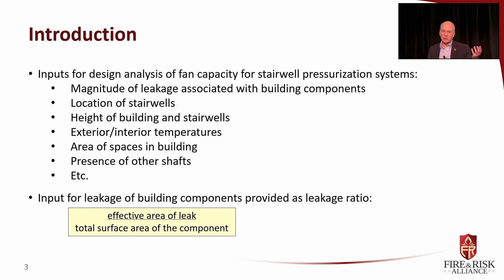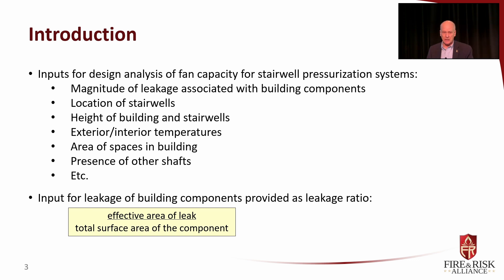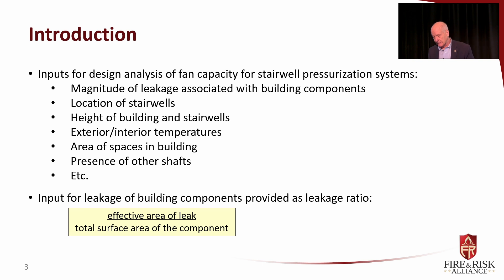We have to account for location of stairways, height of the building and stairwells, exterior and interior temperatures, and areas of spaces. Exterior and interior temperatures were questioned earlier today about stack effects — absolutely, that has to be covered. Areas of various spaces within the building, presence of other shafts, and so on.